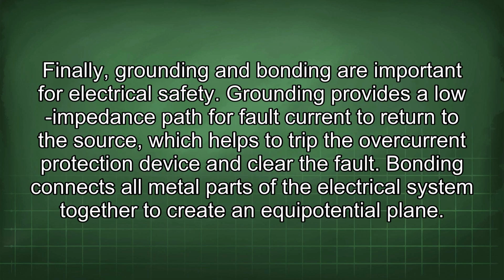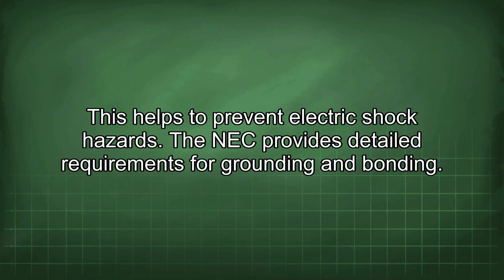Finally, grounding and bonding are important for electrical safety. Grounding provides a low impedance path for fault current to return to the source, which helps to trip the overcurrent protection device and clear the fault. Bonding connects all metal parts of the electrical system together to create an equipotential plane. This helps to prevent electric shock hazards. The NEC provides detailed requirements for grounding and bonding.